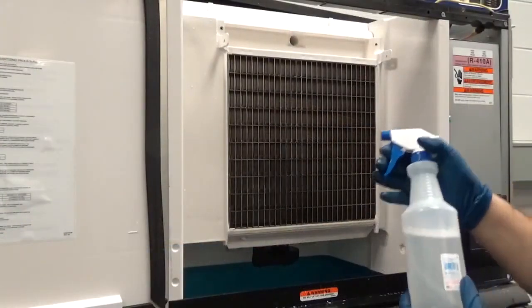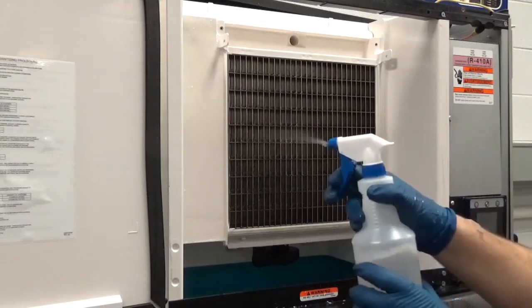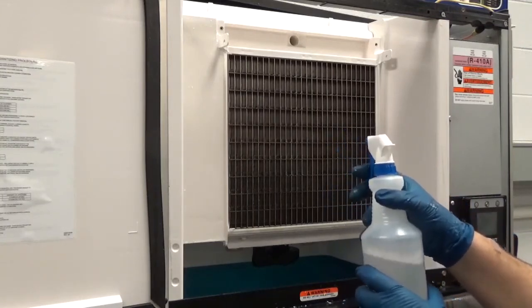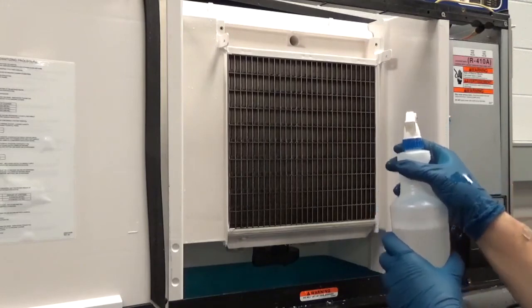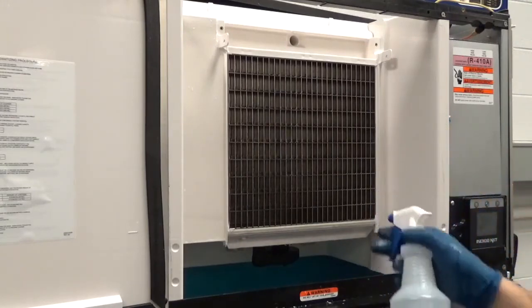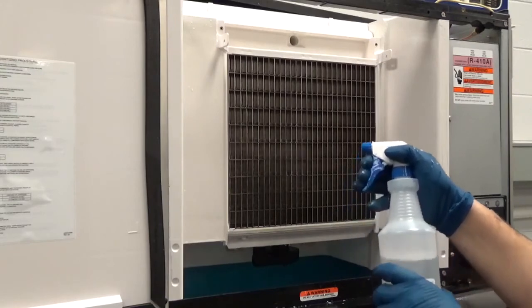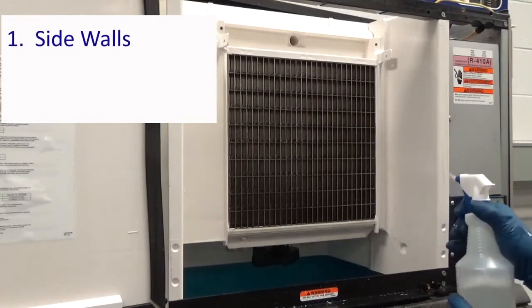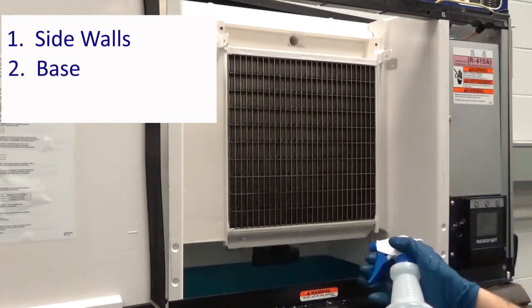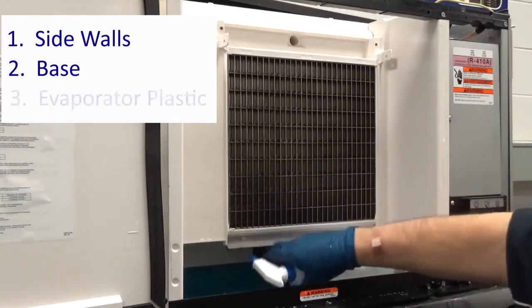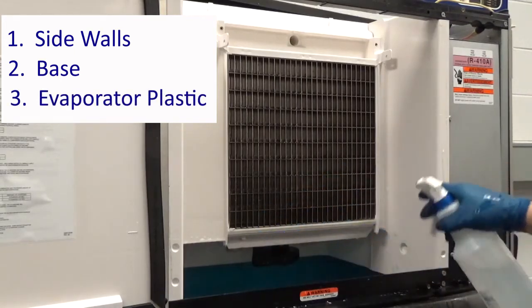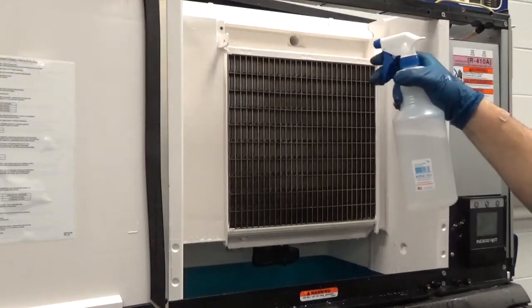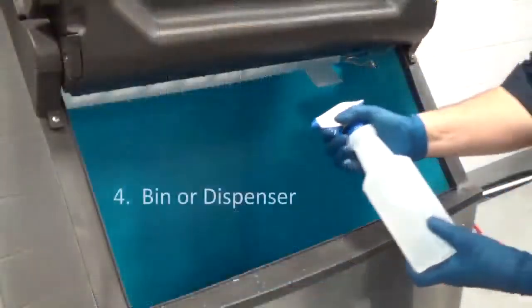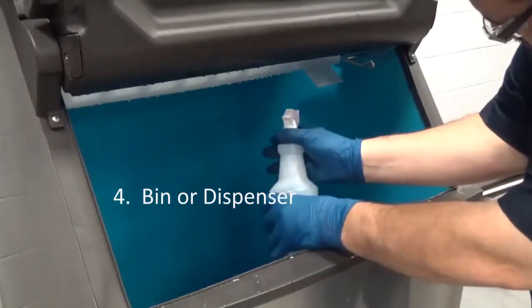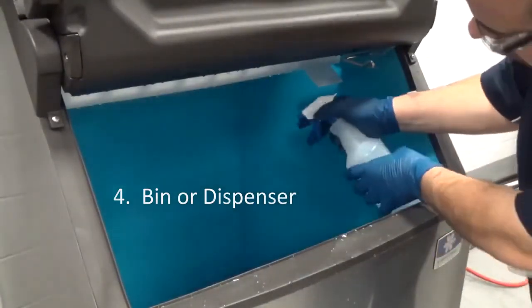Step 11. Use the other half of the sanitizer and water solution to sanitize all food zone surfaces of the ice machine and bin or dispenser. Use a spray bottle to liberally apply the solution. When sanitizing, pay attention to the following areas. 1. The side walls. 2. The base, the area above the water trough. 3. Evaporator plastic parts, including the top, bottom, and sides. 4. The bin or dispenser. Do not rinse the sanitized areas.